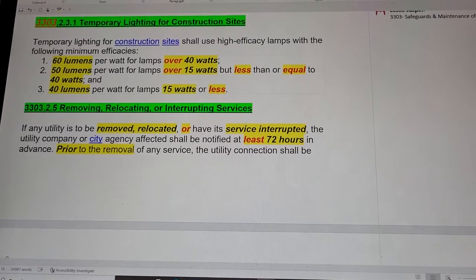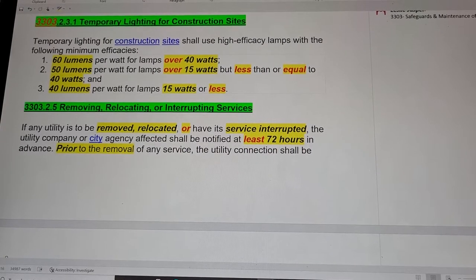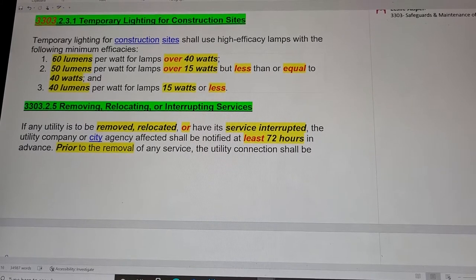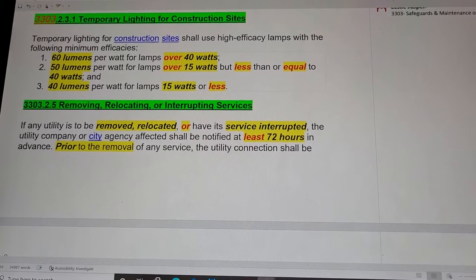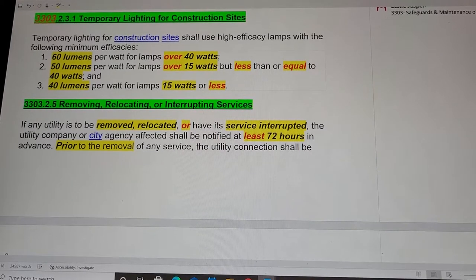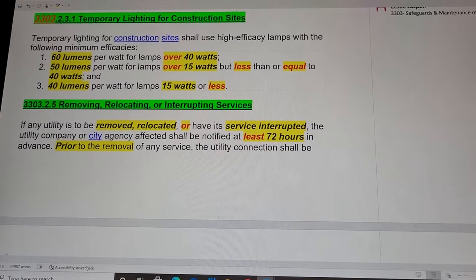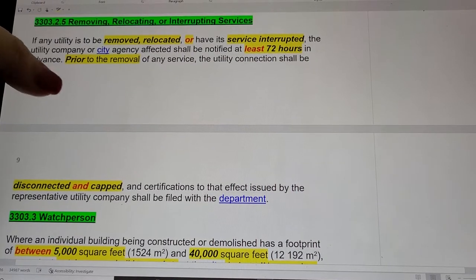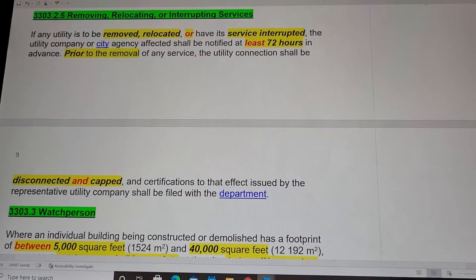60 lumens per watt for lamps over 40 watts; 50 lumens per watt for lamps over 15 watts but less than or equal to 40 watts; or 40 lumens per watt for lamps 15 watts or less. Moving on to 3303.2.5: Removing, Relocating, or Interrupting Services.